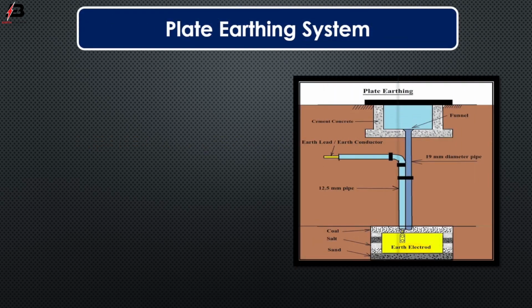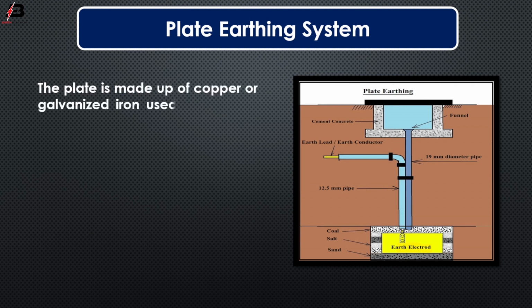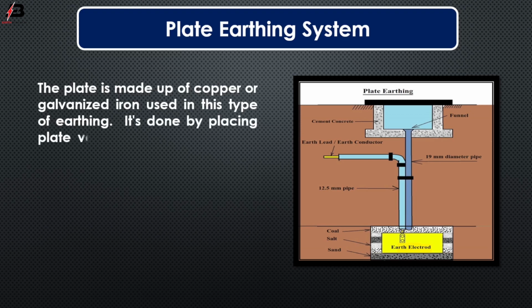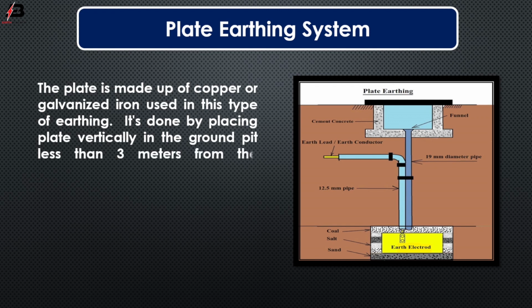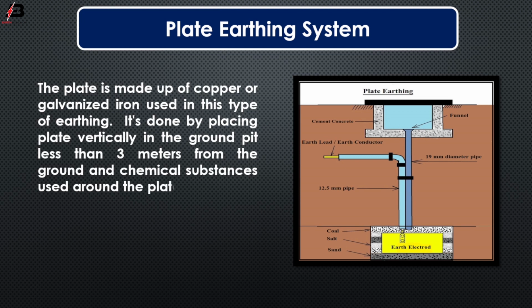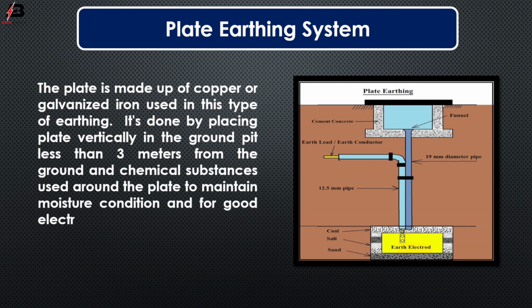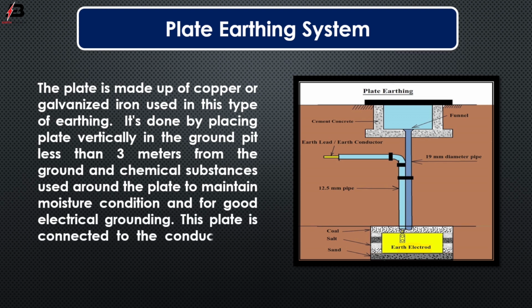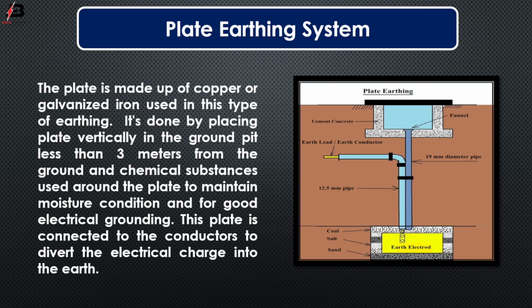Plate earthing. The plate is made of copper or galvanized iron in this type of earthing. It's done by placing the plate vertically in a ground pit, less than 3 meters from the ground, and a chemical substance is used around the plate to maintain moisture and for good electrical grounding. The plate is connected to the conductor to divert the electrical charge into the earth.